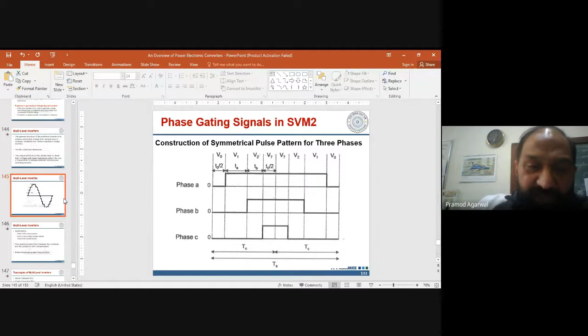If you want higher voltage application, then one method is you use a transformer to step up the voltage, but the transformer cannot be used for variable frequency operation, and therefore we can go for multi-level inverters where each pole can have more than two levels, maybe 3, maybe 4, maybe 5. In that way, without even using transformers, without even switching the devices at higher frequency, we can achieve the output voltage like this.